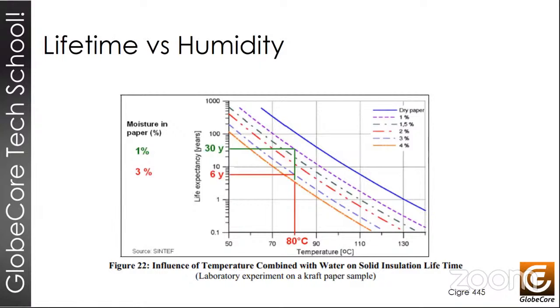The next step is to remove the moisture that we already have in the oil. So in the same Cigre 445 document, we can see this graph of the combined effects of temperature and moisture on the life of the transformer. So you can see here the blue line, the topmost line, and it shows the dry paper in the transformer. And we can see how temperature affects the life of the transformer. We see that for every 8 degrees of temperature, we lose about half of the useful life of the transformer.